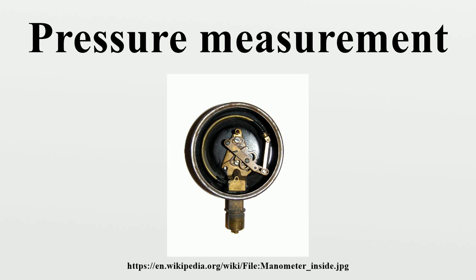An absolute pressure measurement is one that is referred to absolute vacuum. The best example of an absolute referenced pressure is atmospheric or barometric pressure. To produce an absolute pressure sensor, the manufacturer will seal a high vacuum behind the sensing diaphragm. If the process pressure connection of an absolute pressure transmitter is open to the air, it will read the actual barometric pressure. Units. The SI unit for pressure is the Pascal, equal to 1 Newton per square meter.